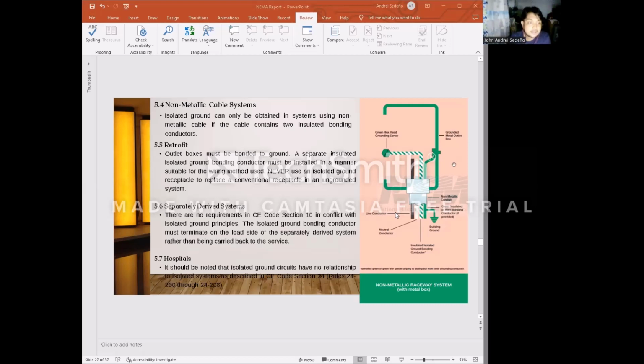Next is separately derived system. There are no requirements in the CE code Section 10 in conflict with the isolated ground principle. The isolated ground bonding conductor must terminate on the load side of the separately derived system rather than being carried back to the service. In hospitals, it should be noted that isolated ground circuits have no relationship to the isolated ground system as described in Canadian Electrical Code Section 24.